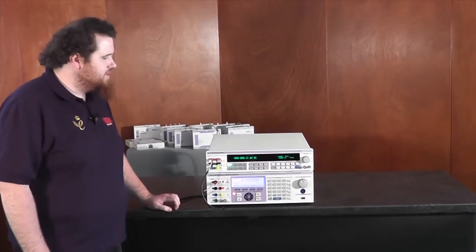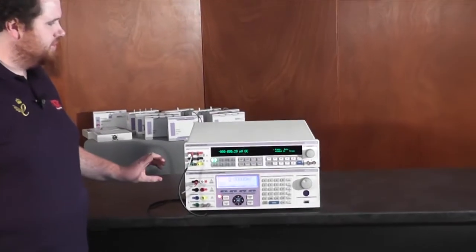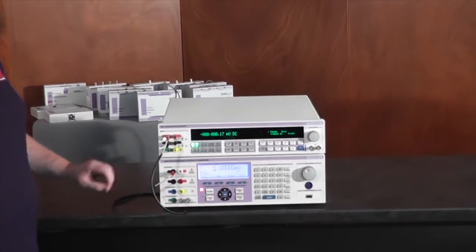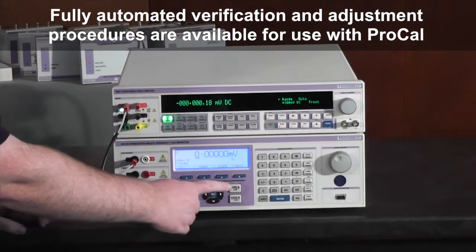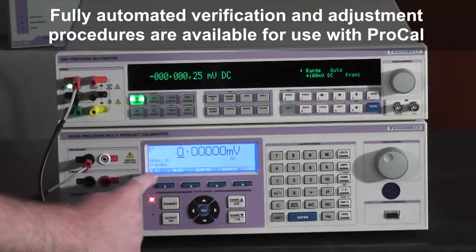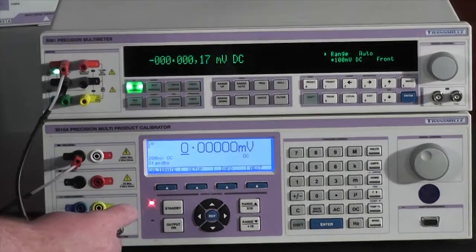The 3000A has been designed to be entirely calibratable from the front panel, with no requirement for a computer. To enter calibration mode, simply press next until calibrate is displayed on the screen.